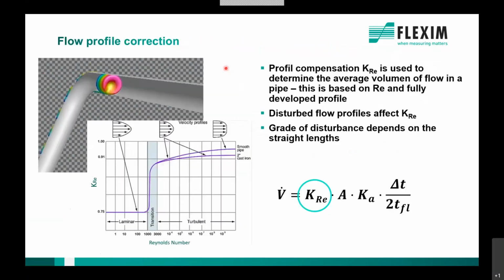Flow profile correction. When we talk about disturbance influences on our meter, we basically look at our K Reynolds, our compensation of the flow profile. What we measure when we send a signal, with the transducers, is the average flow velocity along our path. But what we need to know is the average flow velocity in the pipe. That means we need to correct that measured value with a correction factor called K Reynolds. We need that because the flow in the pipe may look different. We have laminar flow when we have small pipes, high viscosities, or when the flow is very slow.